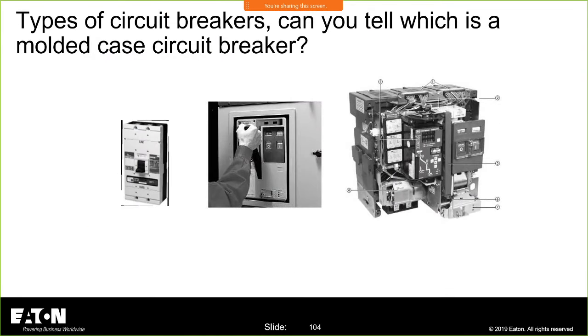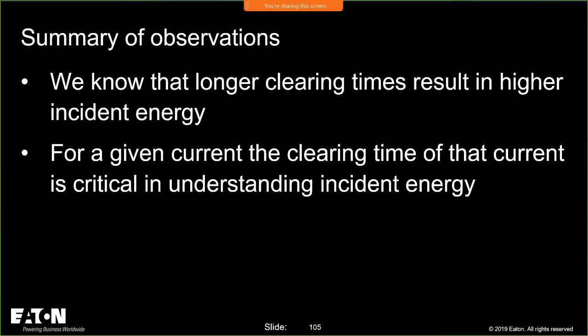And there's my power breaker. You'll notice there's no handle on a power breaker. You have a charging arm in here. Indeed you do. You have a charging arm over here. Indeed you do. But you have push buttons to turn that breaker on and off. A molded case circuit breaker will have that nice little handle sticking out the front. That's how you know you're downstream of a molded case circuit breaker.